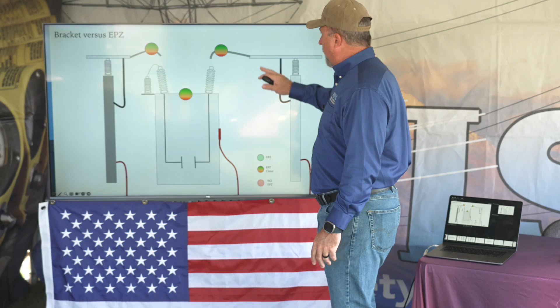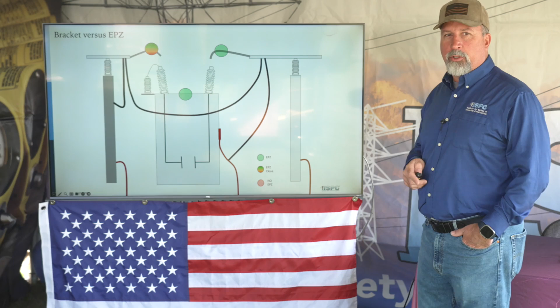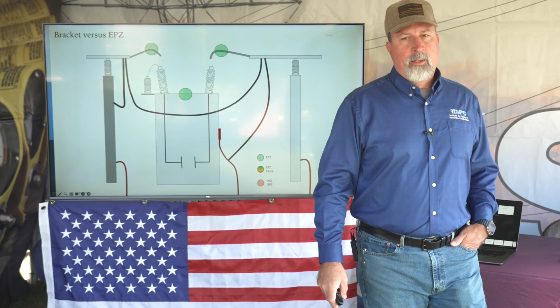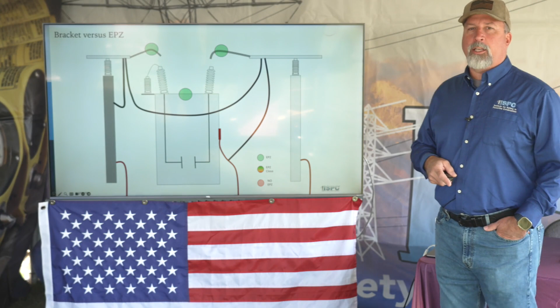Now, as long as there's no fault, as long as you're going to have disconnects open here on either side of this breaker, the only issue here may be induction. If there was a fault out on a line or something, or even internal to the sub with the open disconnects, which just doesn't show, you're going to have that open point. But it's understanding what configuration you have, and what you need to do to eliminate that difference of potential. This ground also could go from here down to here, would do the same thing as jumping across it like that. But it's just understanding where those potential hazards are coming from and how to protect yourself in those instances.